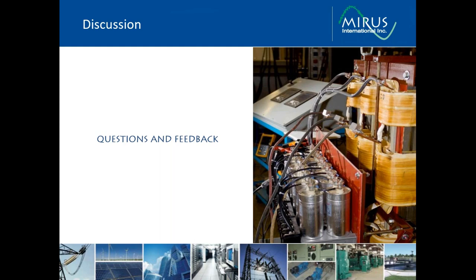But the Mirus filter design is designed with low capacitive reactance and lowers the voltage boost. Our maximum voltage boost is 2.5% at no load conditions, and it also reduces the reactive power, making it compatible with generators. So that voltage boost has not been an issue with our filters.